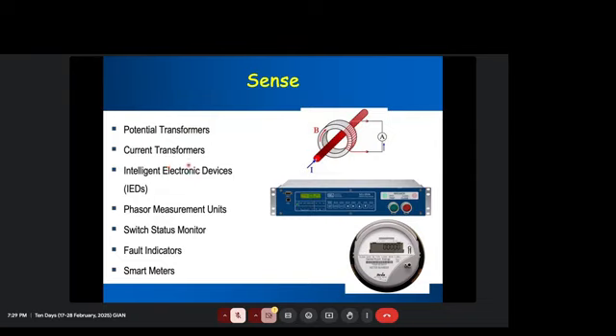So the first thing we do is sense. We already talked about CT and PT a little, but we'll talk more. One thing about sensing is that we cannot afford high voltage directly. We have very high voltage and high current in the transmission and distribution system, and we have to use some kind of electromagnetic principle to lower the voltage down. This is a very simple electromagnetic coupler: this is the wire carrying the current. If you put it around, it introduces a magnetic field which causes current to flow, and we can measure it. The number of turns determines the ratio, which could be 500 to 1, 1000 to 1, or even higher. This is how we get the potential and current transformer.